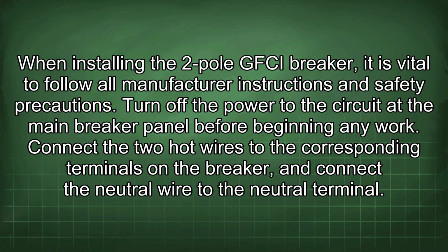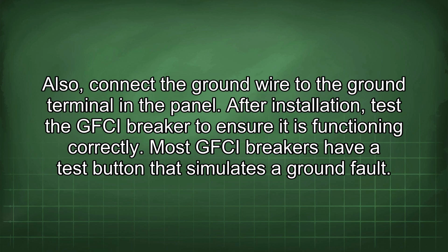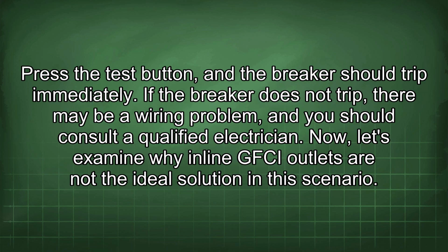When installing the two-pole GFCI breaker, it is vital to follow all manufacturer instructions and safety precautions. Turn off the power to the circuit at the main breaker panel before beginning any work. Connect the two hot wires to the corresponding terminals on the breaker and connect the neutral wire to the neutral terminal. Also, connect the ground wire to the ground terminal in the panel. After installation, test the GFCI breaker to ensure it is functioning correctly. Most GFCI breakers have a test button that simulates a ground fault. Press the test button and the breaker should trip immediately. If the breaker does not trip, there may be a wiring problem, and you should consult a qualified electrician.